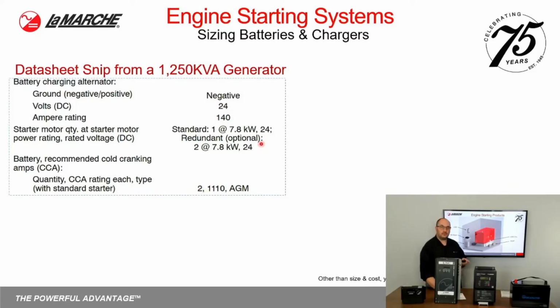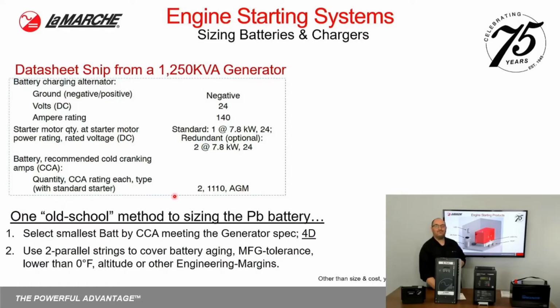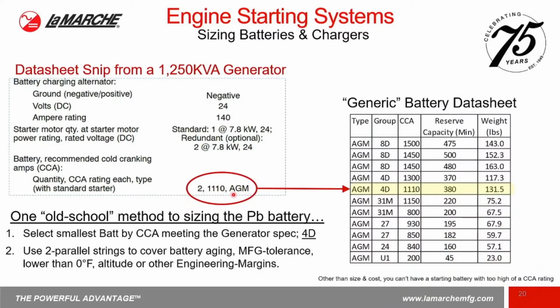So let's look at totally sizing up a system. I took a snip from a 1250 kVA generator, and you can ask around for some independent advice, and here's what one old timer gave me. He said, select the smallest battery by cold cranking amps that meets the generator spec. Looking at this, they're asking for 2, which actually is 2 in series, because the 12 volt BCI batteries are 12 volts, and this is a 24 volt system. So they want 1100 cold cranking amps, and they want it to be an AGM. So we look up our data sheet and we find, lo and behold, here's a 4D battery that meets the cranking requirement.